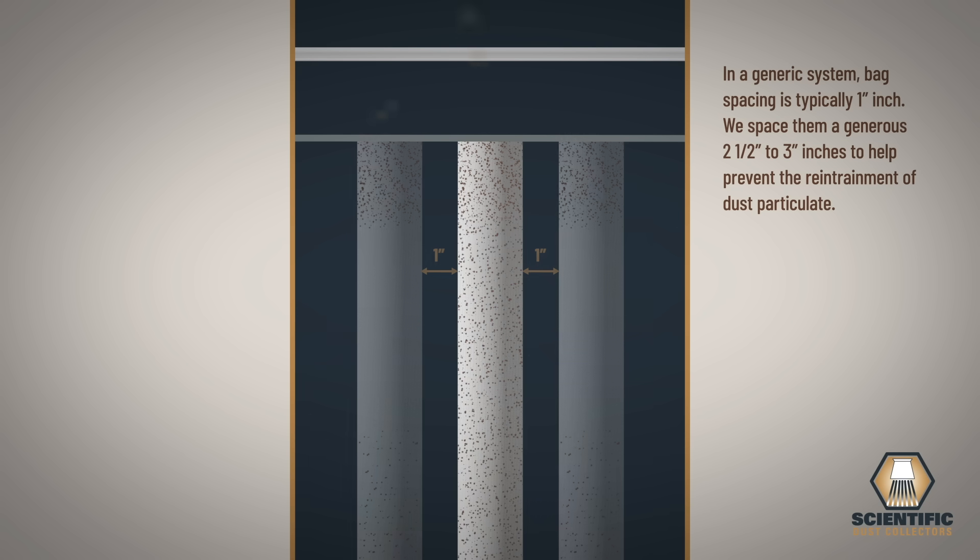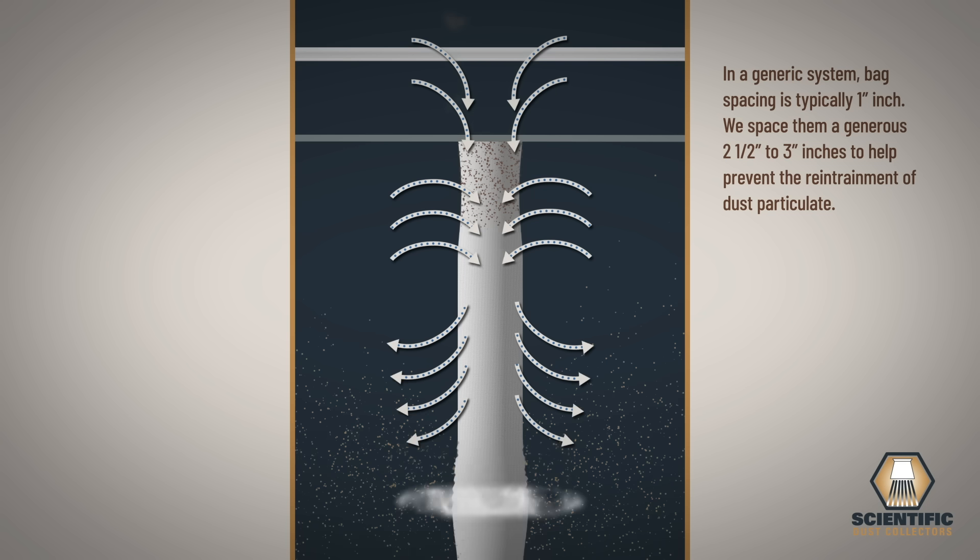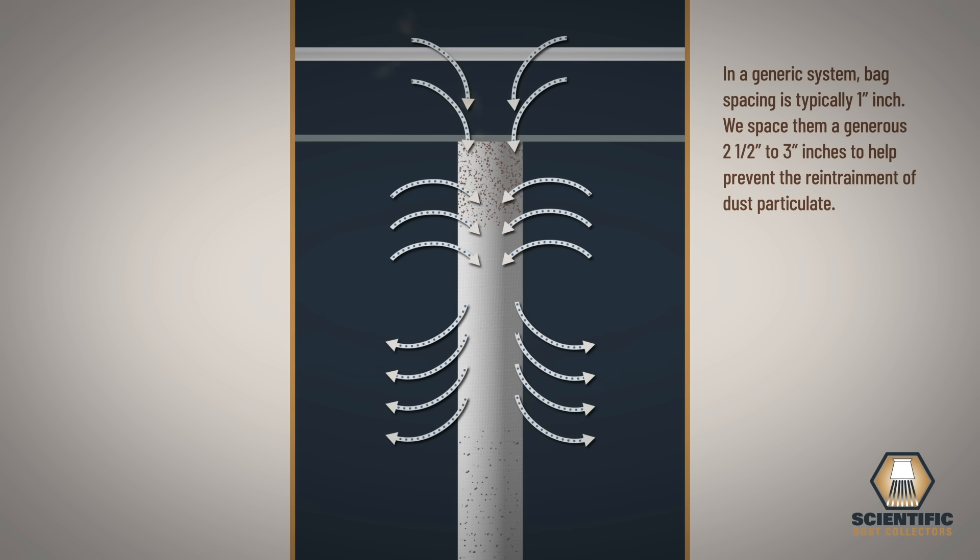This type of cleaning airflow creates a violent shock to the filters, causing excessive wear and can result in puffing when the dust gets driven into the adjoining filter media.